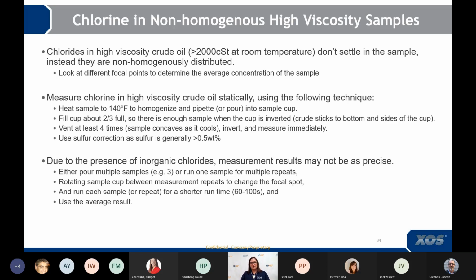One note about these high viscosity crude oil samples is, of course, you're going to have to heat them up to get them in the cup. Now, earlier I mentioned that 5 milliliters is sufficient for most samples. Well, here's the exception. In this instance, you're going to want to fill the cup up 2/3 to 3/4 full, because you want to make sure that there's enough sample when you invert the cup. Of course, the crude oil is going to stick to the bottom and the sides of the cup, and you want to make sure enough sample gets down and goes on top of the film.